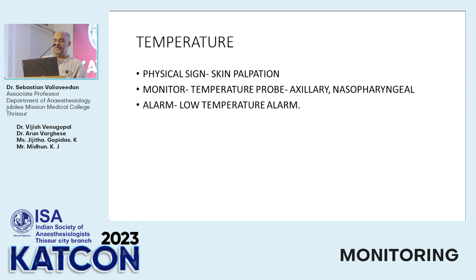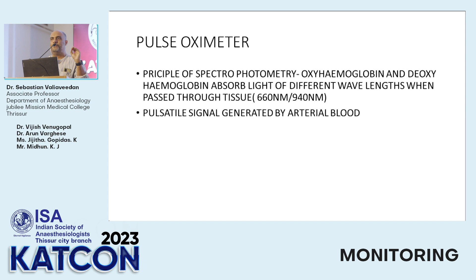Pulse oximeter. Now just a brief two words about the pulse oximeter. So it uses the principle of spectrophotometry, in that the oxidized hemoglobin and the reduced hemoglobin, or the deoxyhemoglobin, will absorb infrared and red lights at different wavelengths, and depending on that, the proportion of the percentages of each can be calculated, that is how the probe is designed. And also, it can differentiate between a pulsatile flow and a non-pulsatile flow. So basically, the percentage of oxyhemoglobin versus deoxyhemoglobin and pulsatile flow versus non-pulsatile flow. This is to differentiate arterial blood from venous blood, capillary blood, and other static tissues. So when you combine these data, you will get the oxyhemoglobin concentration of arterial blood.